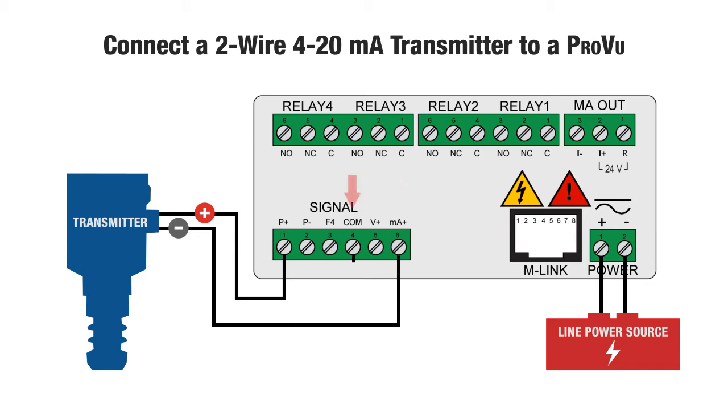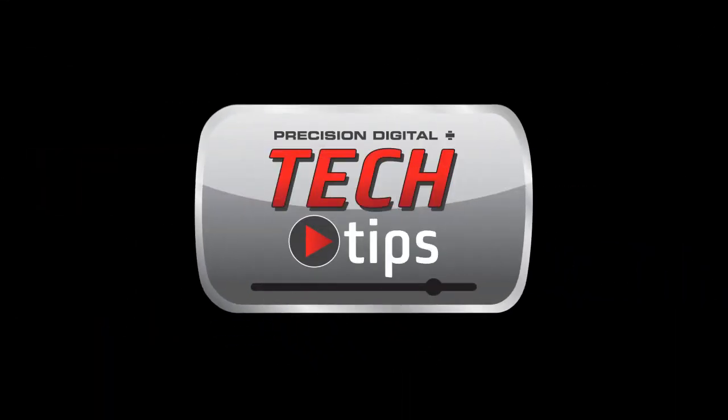Finally, connect the comm terminal of the analog input to the P-minus on the power supply. This is a simple way for the ProVu to act as a meter and a power supply for your 2-wire transmitter. Thank you for watching Precision Digital Tech Tips.